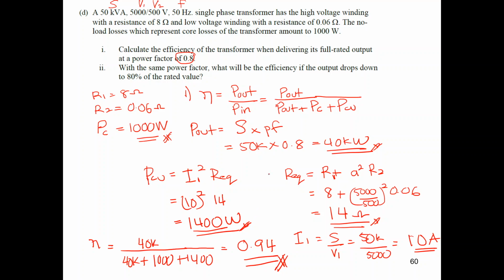To repeat the equation: efficiency equals P out over P out plus P copper plus P core. From the given apparent power S, you can find P out by multiplying by the power factor. P core is given in the problem as 1000 watt. The important part is P copper, which is I1 squared times R equivalent. R equivalent is based on the given R1 and R2, using the formula: 8 plus (5000/500) squared times 0.06, which equals 14 ohms.